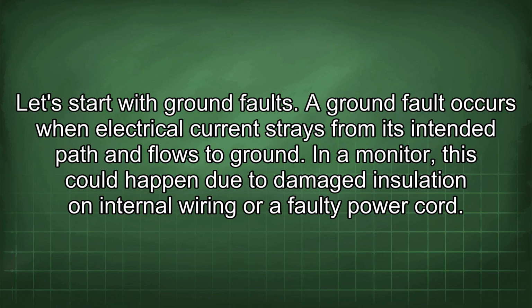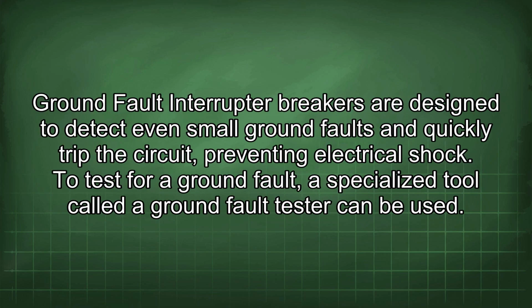Let's start with ground faults. A ground fault occurs when electrical current strays from its intended path and flows to ground. In a monitor, this could happen due to damaged insulation on internal wiring or a faulty power cord. Ground fault interrupter breakers are designed to detect even small ground faults and quickly trip the circuit, preventing electrical shock.